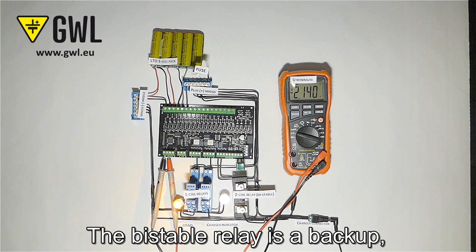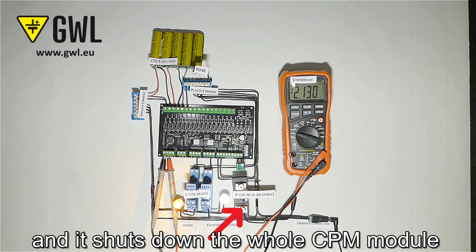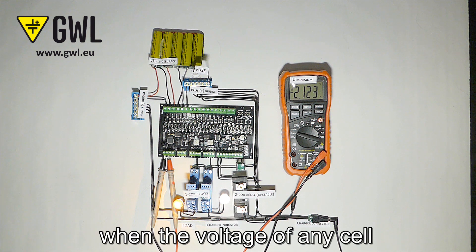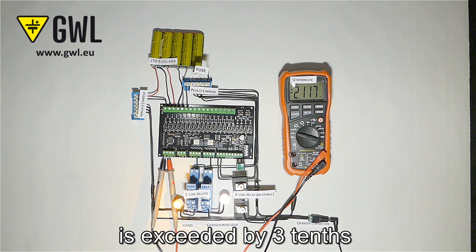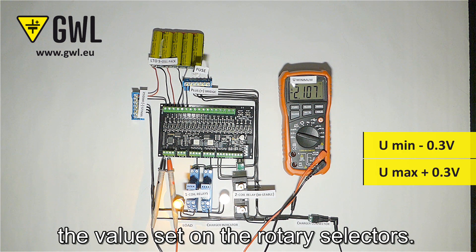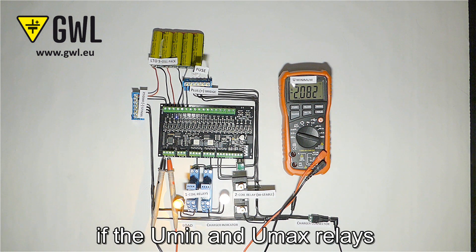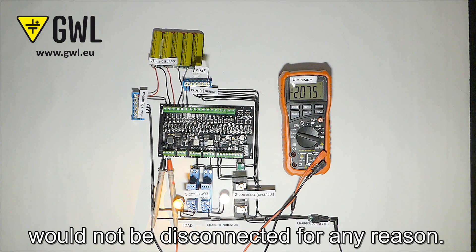The bistable relay is a backup, so called emergency, and it shuts down the whole CPM module when the voltage of any cell is exceeded by three tenths of a volt below or above the value set on the rotary selectors. It serves as a backup if the U-min and U-max relays would not be disconnected for any reason.